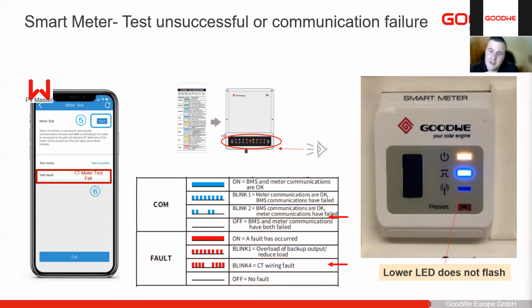So if you do need to have a longer cable for the smart meter, replace the entire cable. Remove the cover out of the inverter. Underneath we'll have those 4 screws. You pull that out, cut the old cable off, feed the new one in, crimp your head on, run your cable to the DB and crimp that end. And then you know you've got one solid cable that will work much better. Also, in the manual is the wiring output. Just a standard B termination is what we use for those RJ45s, but you can refer to the user manual if you have any doubts.